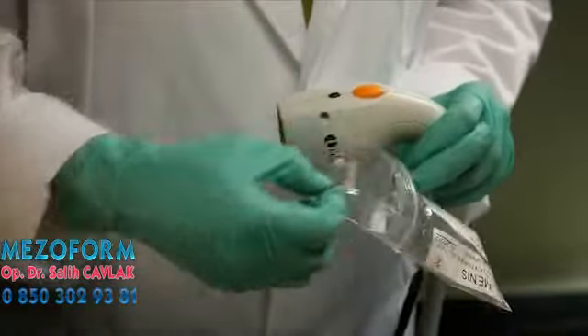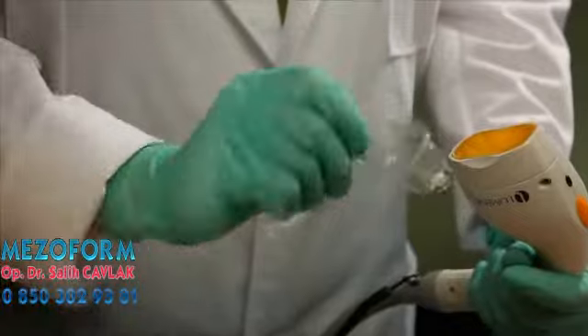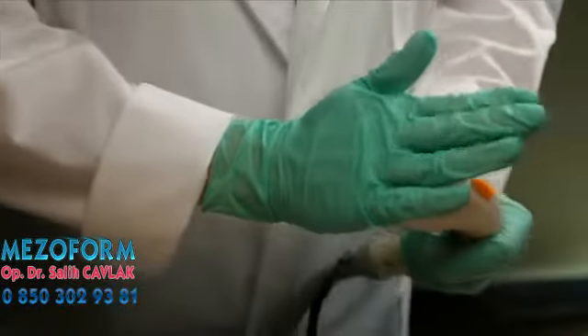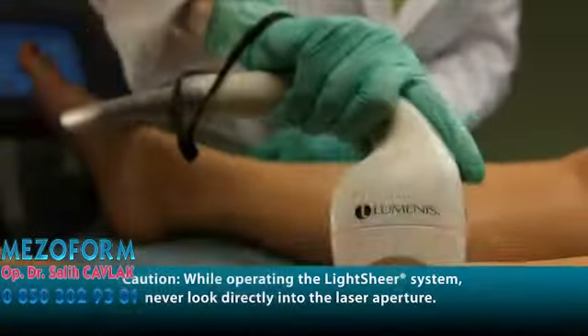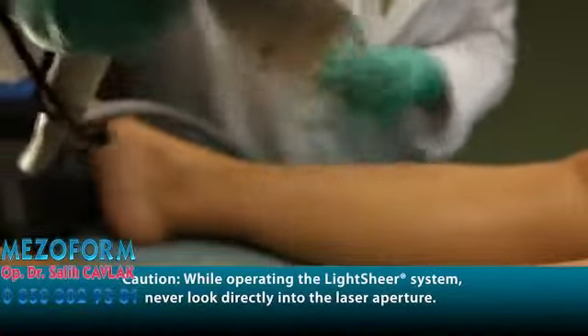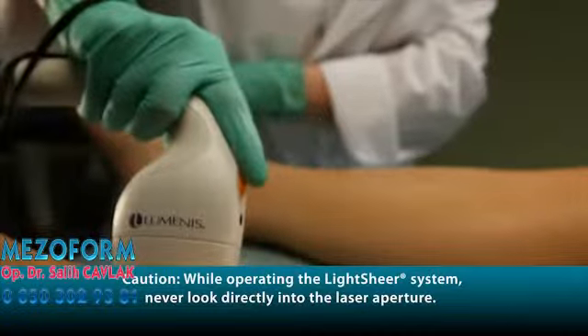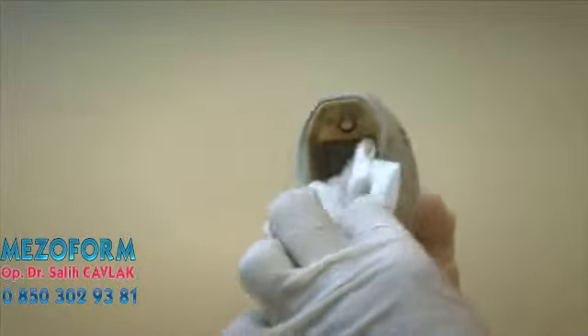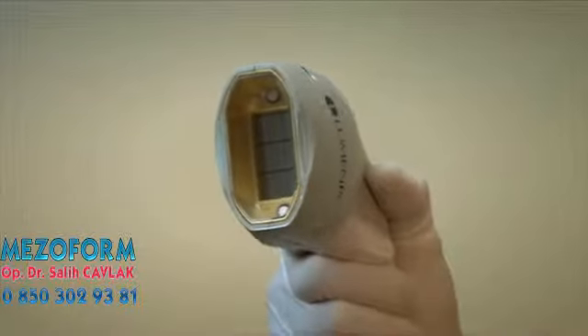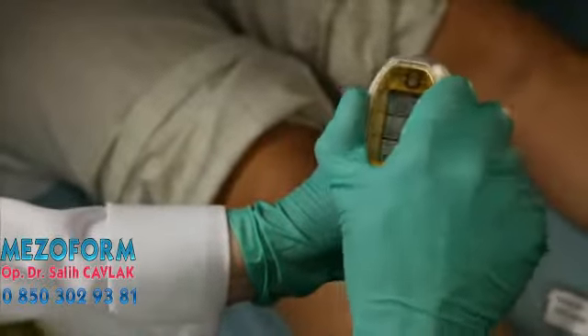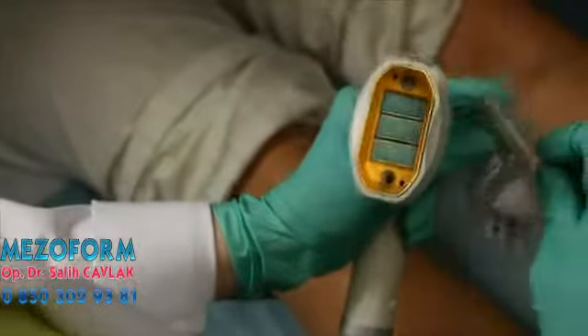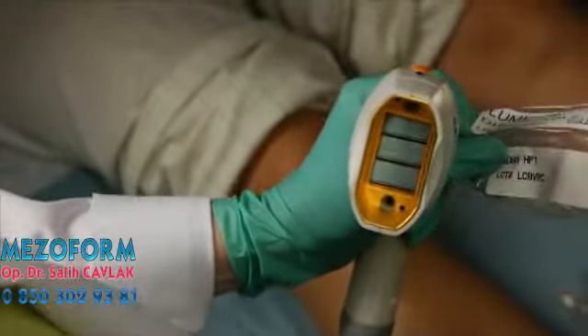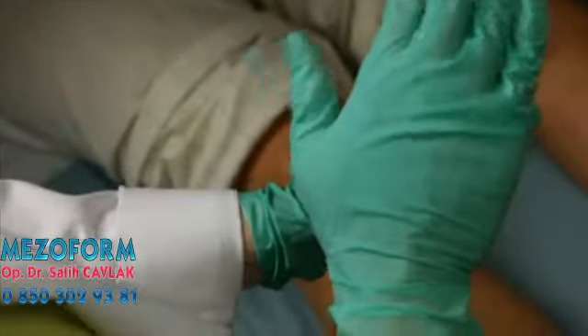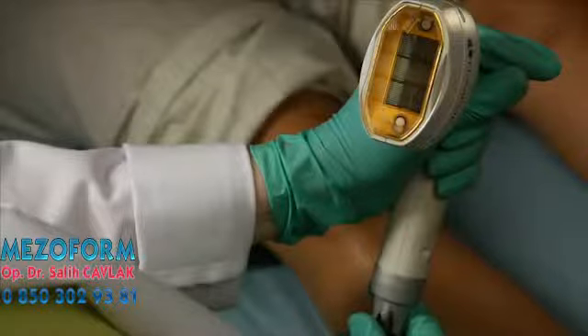After the diode window has been properly cleaned, insert a new and clean disposable insert with a gloved hand to avoid creating fingerprints or contamination. During treatment, observe the disposable insert frequently for debris or damage, using dry gauze to wipe away any contamination. Use alcohol-moistened gauze to clean the disposable insert if dry gauze alone does not remove contamination, if any discoloration or debris is observed in the disposable insert. Immediately insert a new and clean disposable tip when the disposable insert cannot be completely cleaned with alcohol, if smoke is visible after firing the laser, or if a white flash is viewed during treatment.